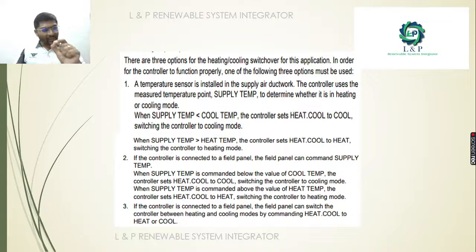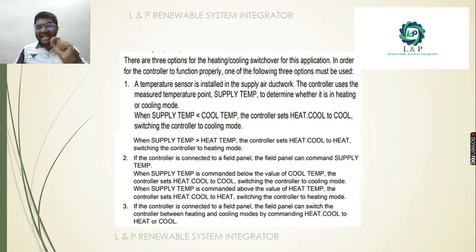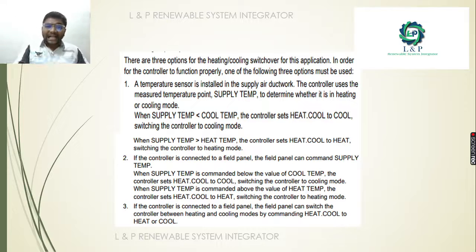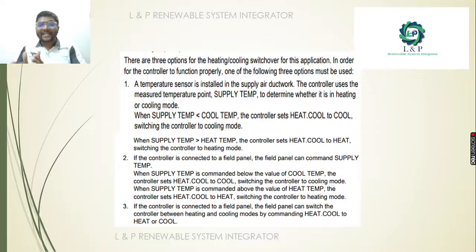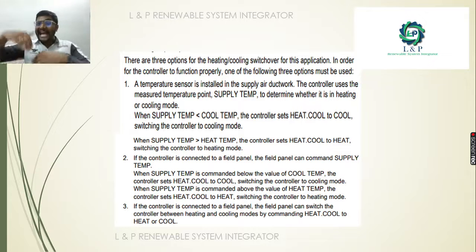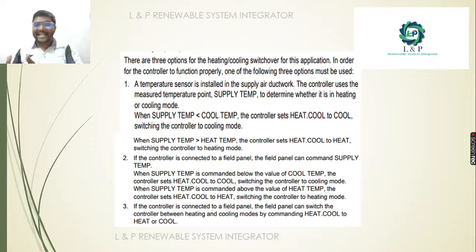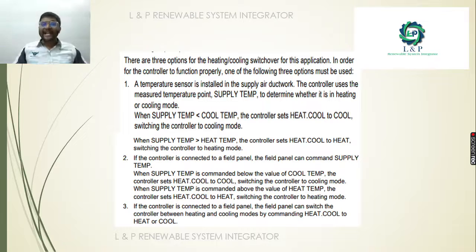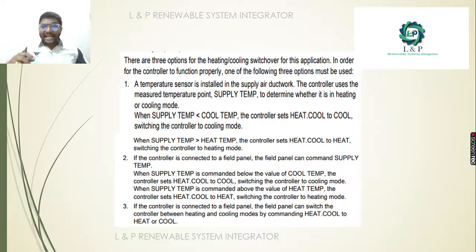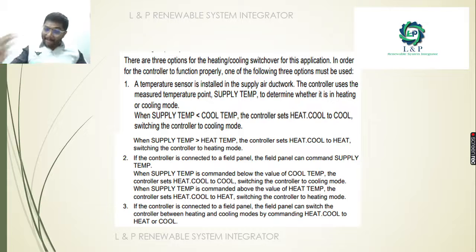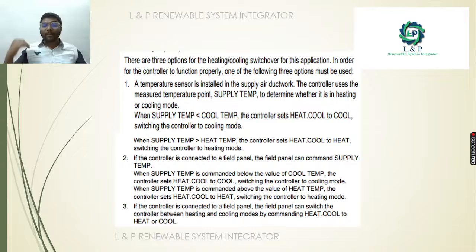For proper functioning, we must follow three methods. First, if a temperature sensor is installed in the supply air duct: if the supply temperature is less than the cooling temperature, it is in cooling mode; if the supply temperature is greater than the heating temperature, it is in heating mode. Second, if a controller in the field panel commands the supply temperature: when commanded below the cooling temperature, it is cooling mode; when commanded above the heating temperature, it is heating mode. Third, if the controller is connected with the field panel, you can switch control between heating and cooling by three commands.